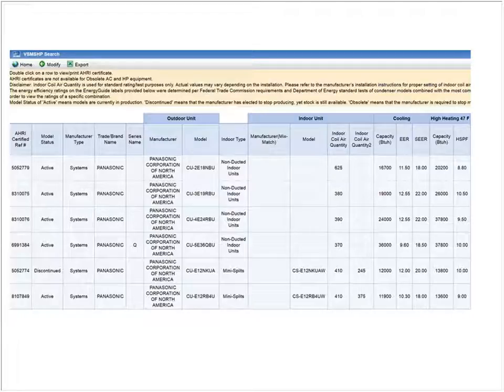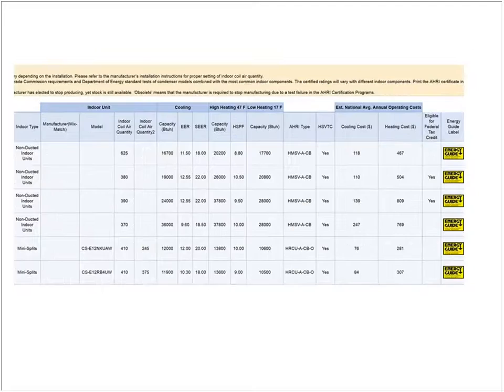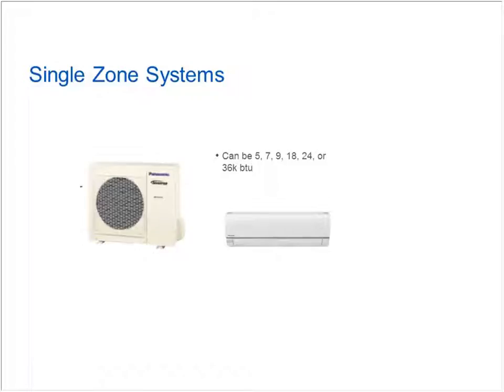It'll tell you if it's a current system, if it's an active system or a discontinued system. It'll tell you the type, the indoor type, whether it's a non-ducted or a multi-split, mini-split. And then it'll start giving you all of the data: the cooling, the high heating. And my favorite, as I go across the page, is low heating, right? So what's the BTU output at 17 degrees?